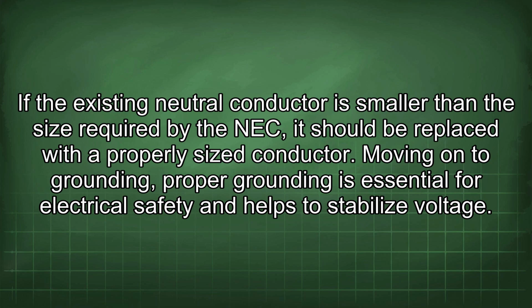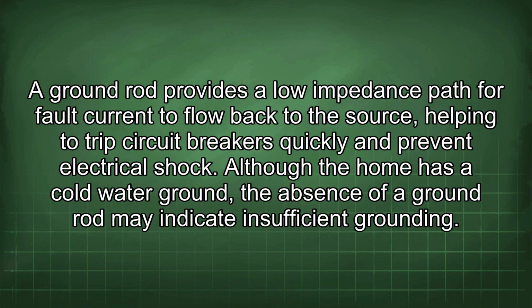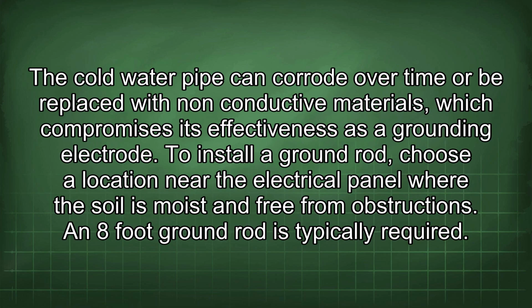Proper grounding is essential for electrical safety and helps to stabilize voltage. A ground rod provides a low impedance path for fault current to flow back to the source, helping to trip circuit breakers quickly and prevent electrical shock. Although the home has a cold water ground, the absence of a ground rod may indicate insufficient grounding. The cold water pipe can corrode over time or be replaced with non-conductive materials, which compromises its effectiveness as a grounding electrode. To install a ground rod, choose a location near the electrical panel where the soil is moist and free from obstructions. An 8-foot ground rod is typically required.